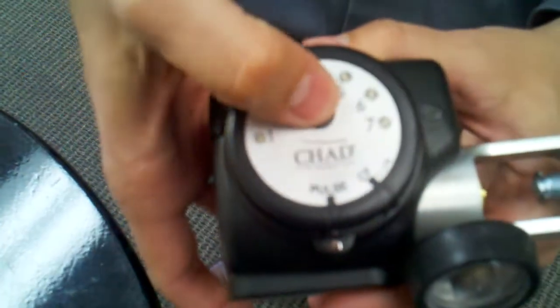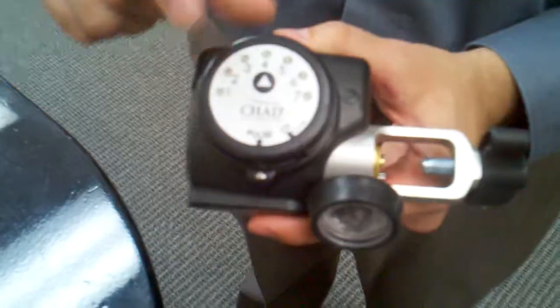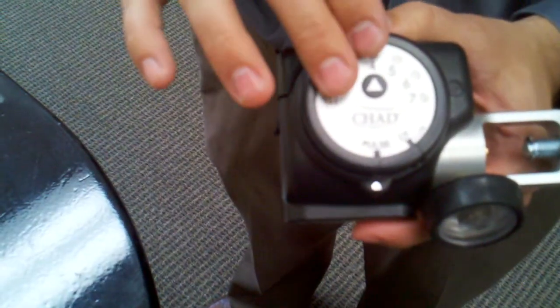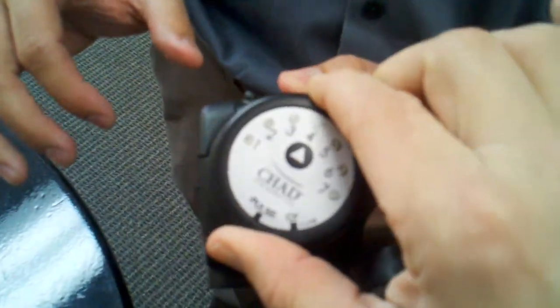To adjust this unit, all you have to do is push this little knob — real easy. Every time you take a breath, a light will indicate that you are taking a breath, similar to a portable concentrator lighting up green. Also, by switching it from pulse to continuous and back to pulse, it's going to remain on the last liter flow you had set. Once you set the pulse dose to your setting and need continuous flow, you never have to worry about coming back to the knob.